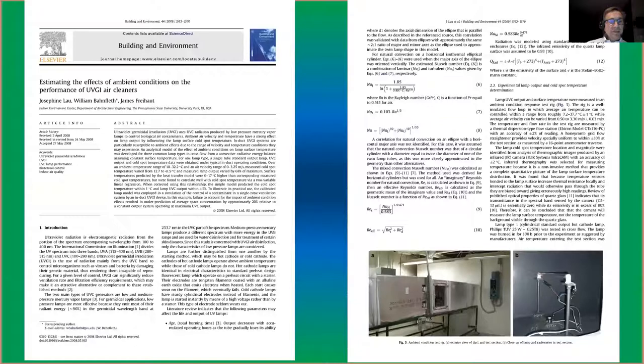It's a landmark study that shows that UV lamps are sensitive to airflow and to cold airflow. It's called the wind chill effect. UV lamp output is dependent upon the amount of mercury that's vaporized inside the lamp. If the lamp is cooled by a cold airflow, and typically when it's placed perpendicular to the airflow, its output can drop dramatically. It can drop by 50%. And if you don't use a reflector or protect the lamp from this cooling when you're putting it in cross-flow position, the output can be basically half of what you expect. And the disinfection will not be as good.